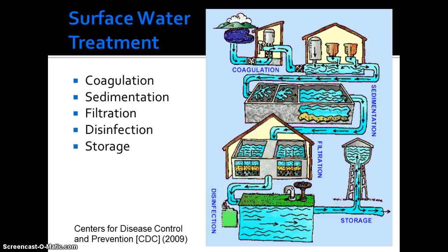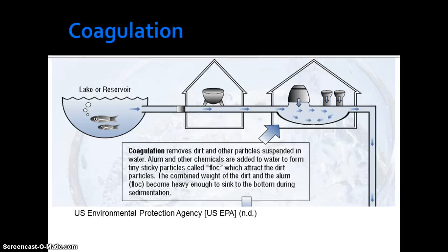As the U.S. Environmental Protection Agency, U.S. EPA, notes, water treatment may vary by community depending on the quality of the water entering the plant. Groundwater typically requires less treatment than surface water from lakes, rivers, and streams. The first step shown is coagulation, though there may be pretreatment screening to remove any large debris that would impede water treatment. Coagulation removes dirt and other particles suspended in water. Alum and other chemicals are added to water to form tiny, sticky particles called floc, which attract the dirt particles. The combined weight of the dirt and the alum floc becomes heavy enough to sink to the bottom during sedimentation. (U.S. EPA, no date.)